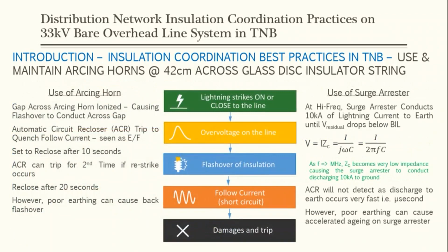Okay, and like I've said before, when lightning strikes on or close to the line, it will cause overvoltage on the line, and because of that, there will be flashover of insulation. So with the use of arcing horn, where we have the gap across the arcing horn, the air will be ionized, causing flashover to conduct across the gap. But with this flashover of insulation, it will cause follow current or a short circuit, and our protection relay will see it as an earth fault.